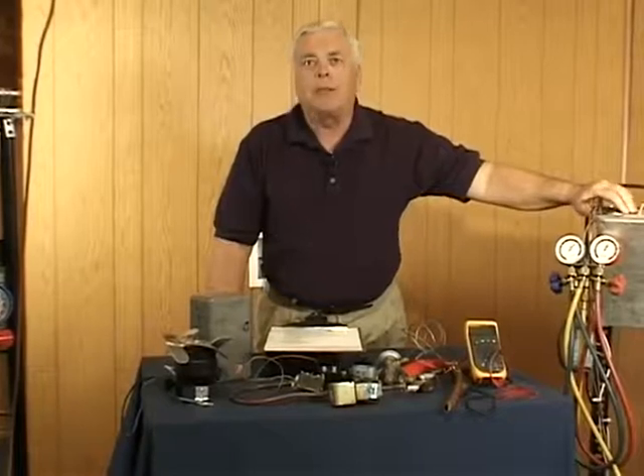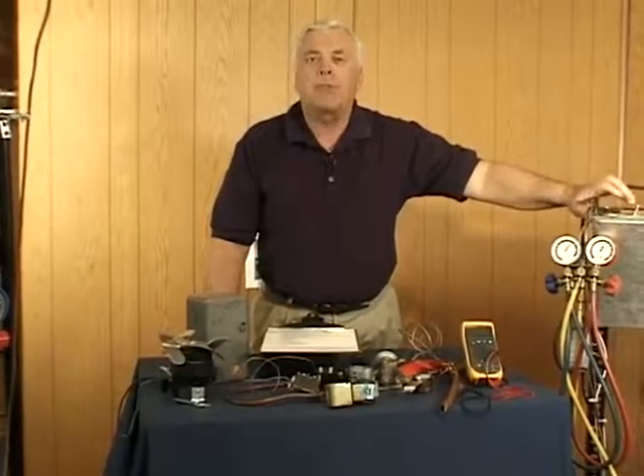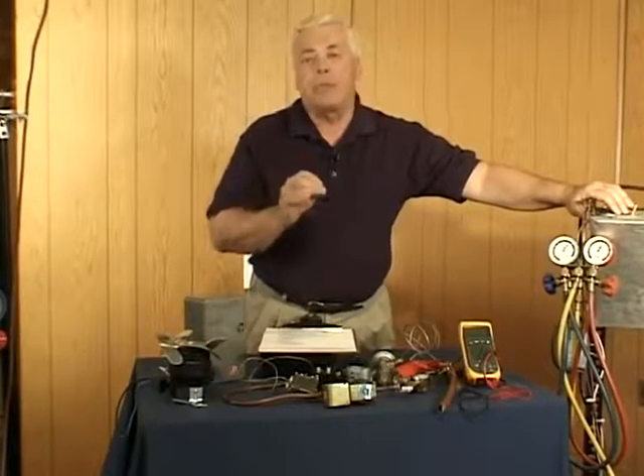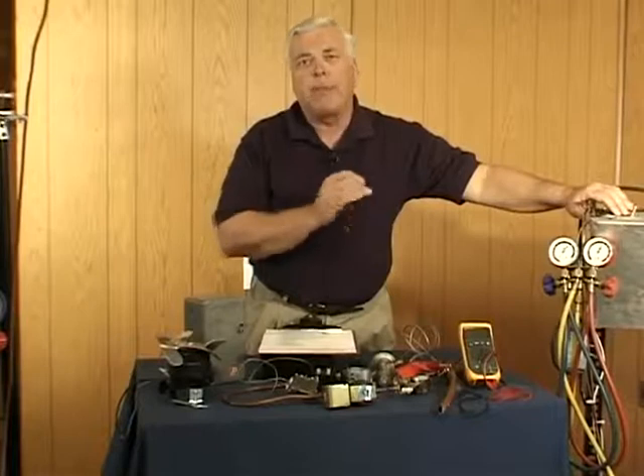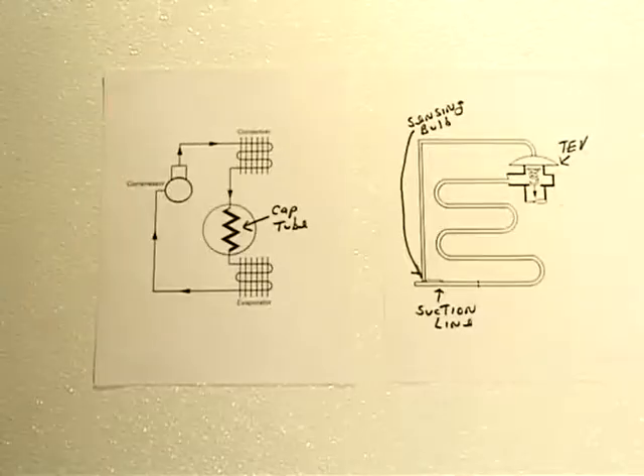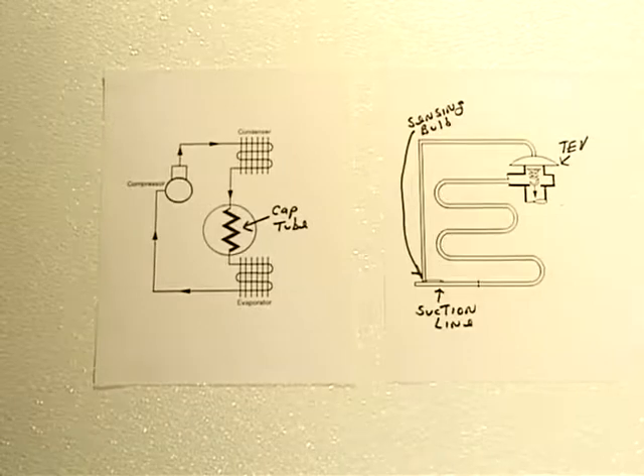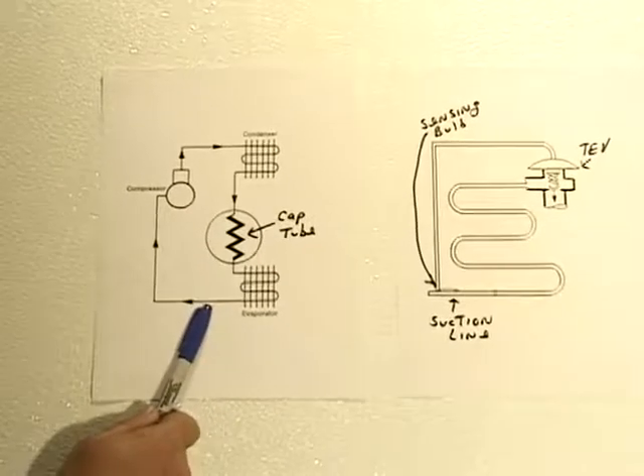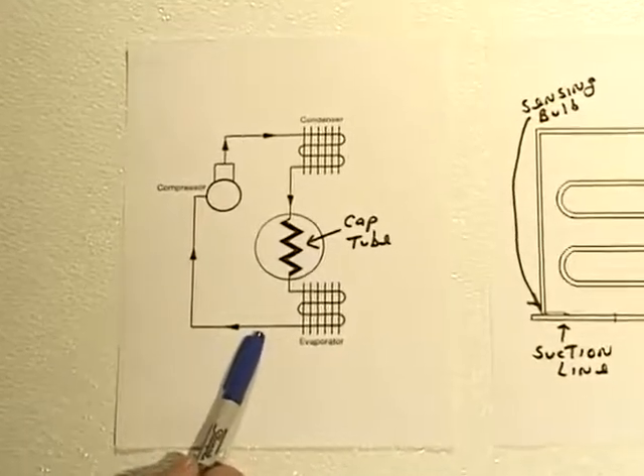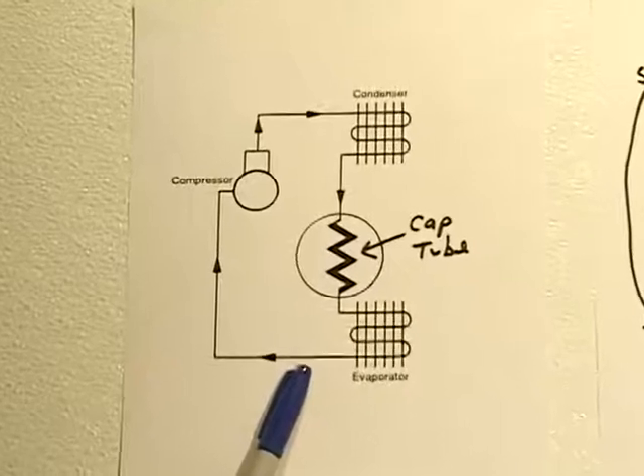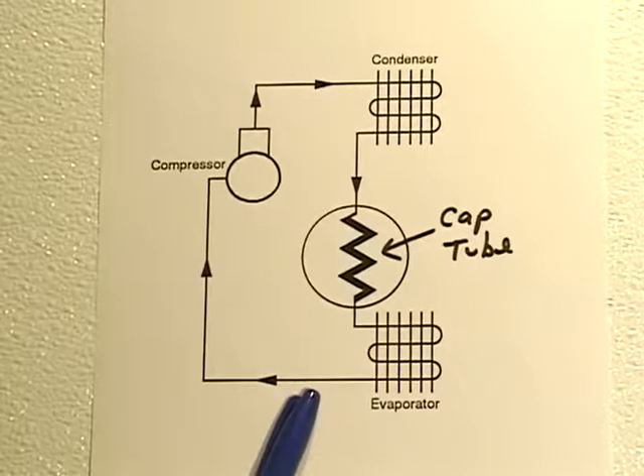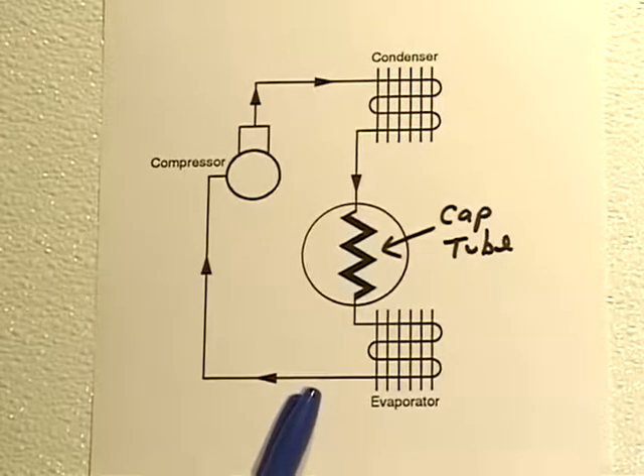We're going to get started with some graphics that compare capillary tube systems found in domestic refrigeration systems and thermostatic expansion valve systems found in commercial refrigeration. We'll look at the two types of refrigeration systems you may encounter in reach-in freezers and reach-in refrigerators. On the left is a simple capillary tube system that's been used for many years in domestic refrigerators and freezers, though it's also possible you may find this type of system in a commercial reach-in refrigerator or freezer.